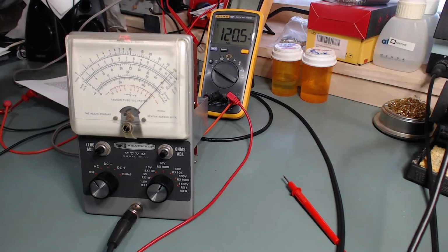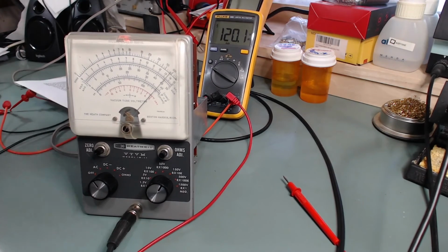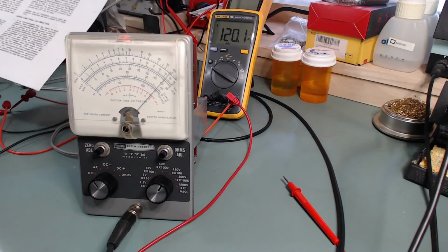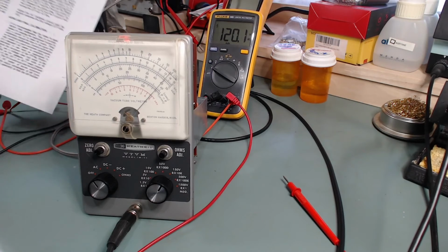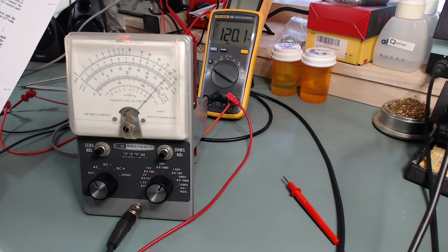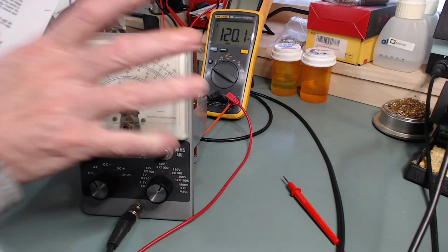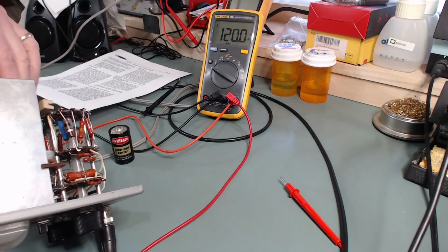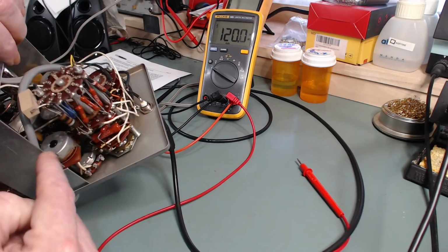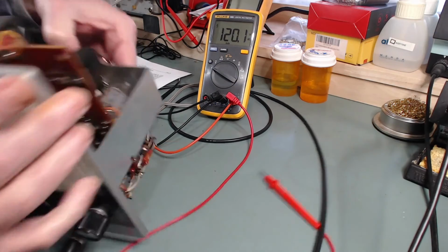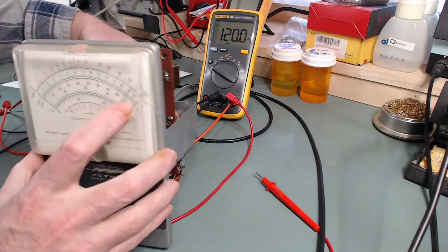I'll tap this variac here a little bit, see if we can't get down to 120, 120.1. That's pretty close, and that's a good representation of line voltage. Now, what we want to do is set the AC calibration, which is this pot right here. AC cal is right there, and we just want to set this to read 120 volts.